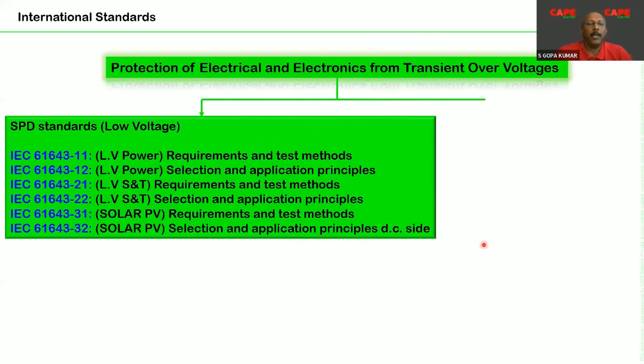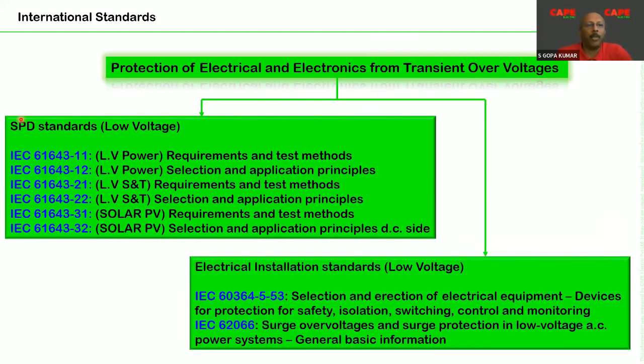Now, coming back to the presentation, international standards. Surge protection is carried out based on two main standards. The first one, on the left side, is the SPD standards, made by SC 37A, which is basically for low voltage, that means up to 1000 volt AC and 1500 volt DC, for power line, data line, signal line, and solar PV. You can see the standards named 61643-11, 11 or 21, 31. These are for requirements and test methods, and 12, 22, 32 are the selection and application principles. So these are the SPD standards.